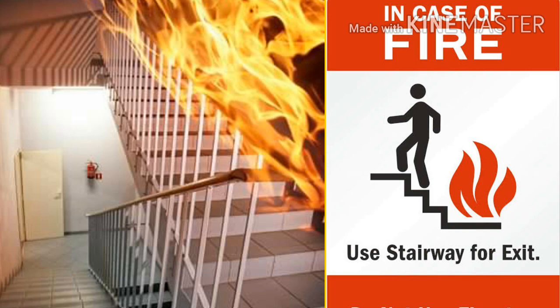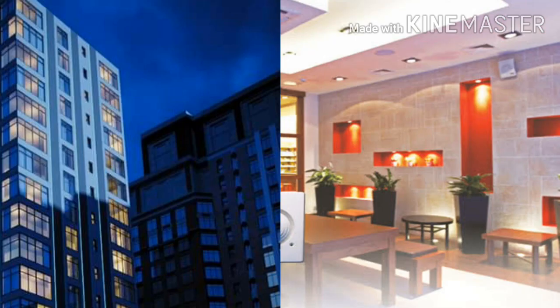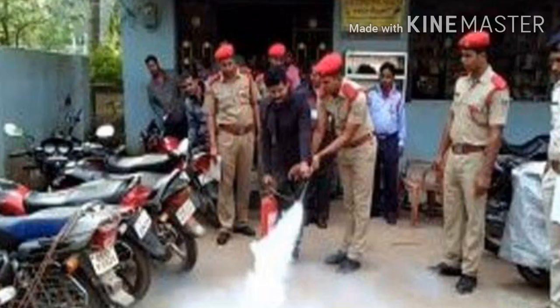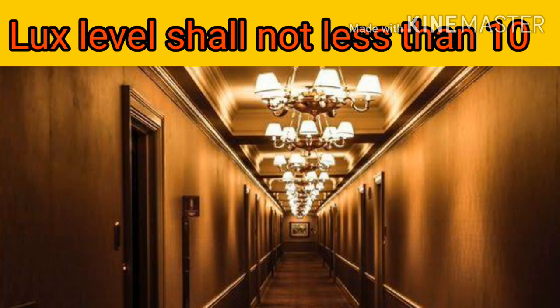And the floors of exit shall be illuminated. All points include the turning points, intersections of corridors and passageways, staircases, landings and discharge exit at ground level. The intensity of lighting throughout shall not be less than 10 lux measured at floor level. And lights recessed in the walls and floors at about 30 centimeters above the floor level are recommended, as they are not going to be obscured by smoke. Illumination lights shall be so arranged that failure of a bulb or connection will not leave any area in total darkness. Okay, next, emergency power supply and lighting.